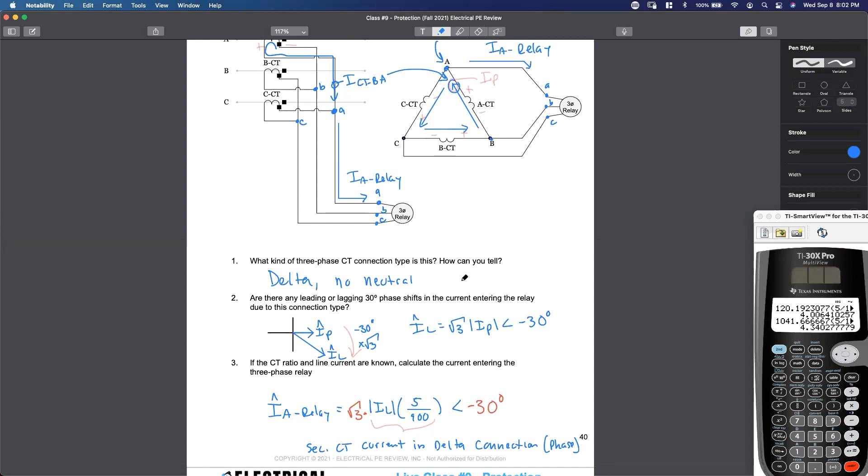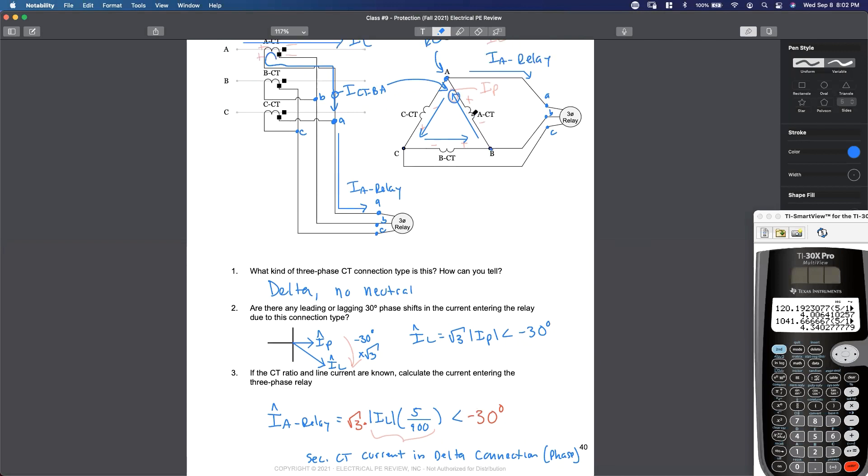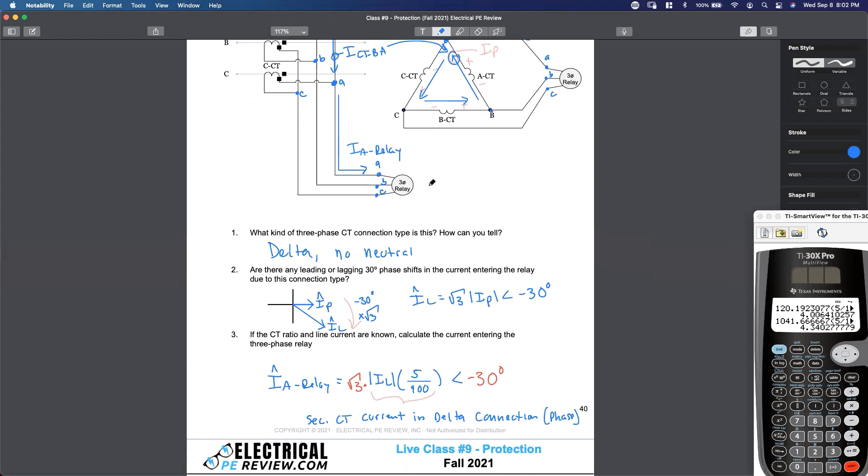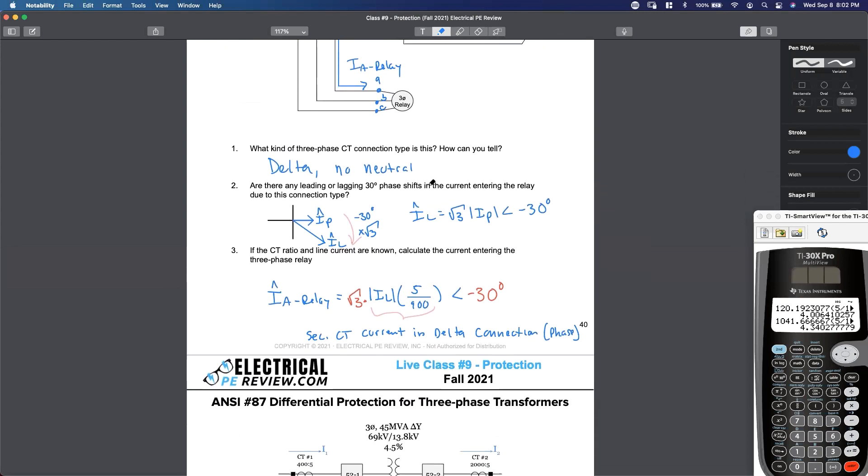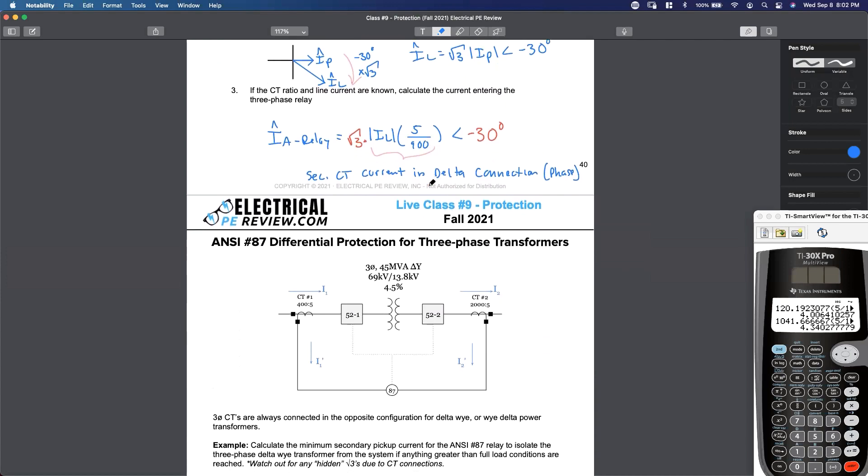All right. So now, Mo said, shouldn't it be I phase then? This is I phase right here. From here to here, right? From here to here is your secondary CT delta phase current. When we multiply these secondary CT delta phase current by the square root of three, and we lag it by 30 degrees, now we just left the delta connection, and now we're entering the relay. Let's see how this applies to differential protection of a three-phase transformer.